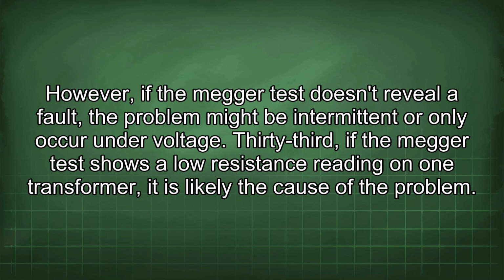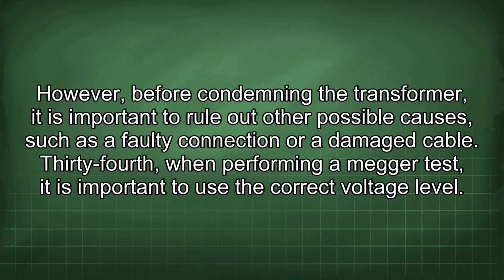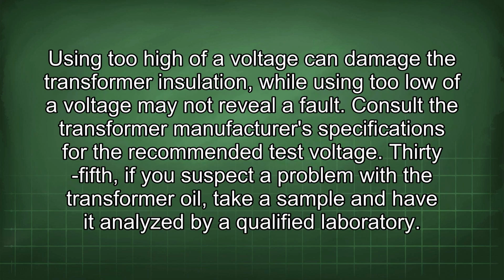33rd, if the megger test shows a low resistance reading on one transformer, it is likely the cause of the problem. However, before condemning the transformer, it is important to rule out other possible causes, such as a faulty connection or a damaged cable. 34th, when performing a megger test, it is important to use the correct voltage level. Using too high of a voltage can damage the transformer insulation, while using too low of a voltage may not reveal a fault. Consult the transformer manufacturer's specifications for the recommended test voltage.